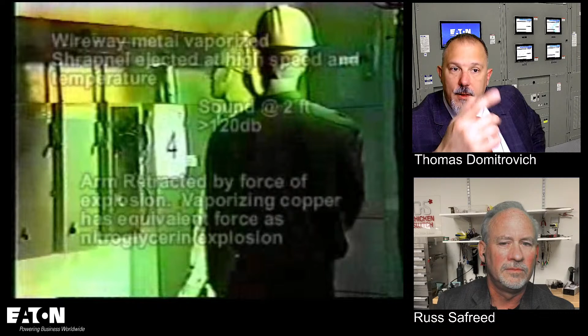I used to think that the energy went up through the conduit and pushed it out - at least that's how I used to tell people - until I talked to Vince Saperita and Tim Sternko, who were in the room when this happened, and they said, 'No, that's not the way it went.' He says the reason that thing popped off was because of the magnetic forces with the wire - they bounce around in there, and it was strong enough to blow that wireway off.